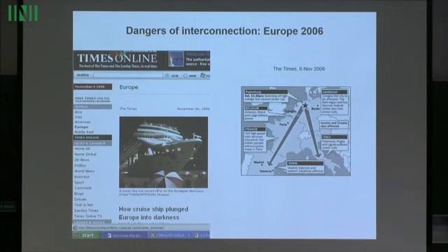So there was no danger of electrocution. Then, a couple of hours before the event, they changed the timing - nothing special about it, they do that kind of thing all the time. But for whatever reason, that day they brought forward this hour, and the local utility, E.ON, should have done the calculations to make sure that if they switched off that line, nothing bad would happen. They hadn't done that - they trusted their judgment and said everything would be fine. Well, it wasn't, because then you had this cascading event: when they did trip that line, the other lines got overloaded.